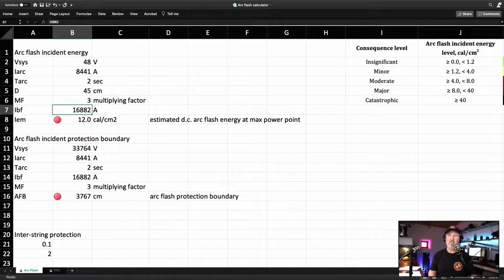Right, so I plugged in the bolted fault current for one string, and straight away it's calculated the arc flash incident energy and the arc flash boundary, the distance within which you need to wear PPE. That's 3.7 meters, and I've only done it for one string of these 1500 amp hour cells. But the reason it's getting a red flag, that little red dot, is telling me that it's a very high level of arc flash energy and the PPE requirements are quite severe.